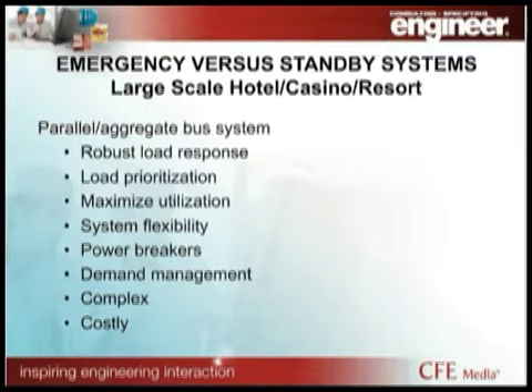I do want to mention, you can also do cold bus paralleling. That's where, on your smaller systems that we do for paralleling, your generator bus sits dead. When you lose your load, you may have transfer switches downstream. You create the aggregate bus with the generators, and then you distribute through the transfer switch in a more conventional approach. It's a hybrid of the extreme paralleling system and the traditional system of generator with transfer switches. There's a lot of system flexibility you can build into this. Typically, we would use power circuit breakers as transfer pairs. Those are power devices, the type of breakers that you're going to rack out, and they're designed and intended for switching purposes. Some of the disadvantages: it can be very complex, and Gerald referenced the KISS principle, and there's ways to execute the KISS principle within this type of system, which we'll talk about a little bit later.